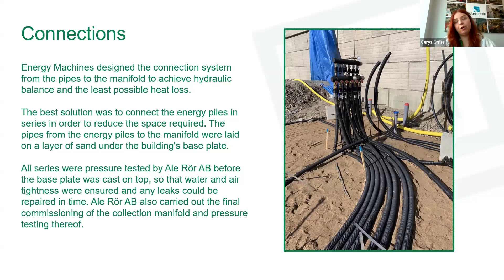So how this works day to day is that the manifold feeds into a heat pump, like one that would be used for an air source or a ground source heat pump, and that feeds heating and cooling to the building through a standard HVAC system. Working with Energy Machines, we were able to optimize this system as much as possible. So all these pipes and the way in which it moves through the building were designed specifically to ensure the least possible heat loss and cooling loss, dependent on the time of year. And as originally planned, the system does deliver all heating and cooling needs of the building with no requirement for an external energy source.